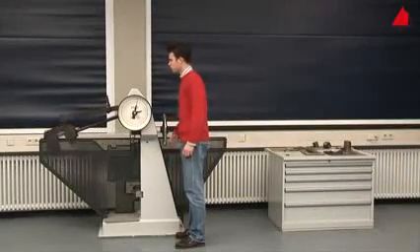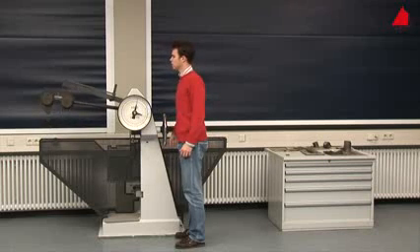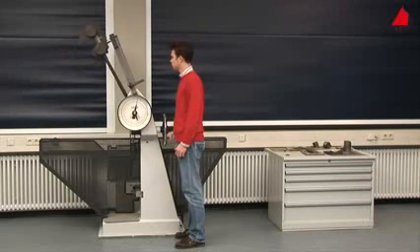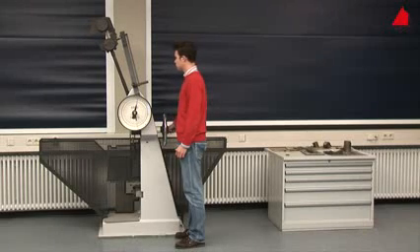The pendulum on the machine has a heavy weight at the end. This is lifted into the starting position in step one. Then the tester checks whether the testing machine has been adjusted accurately.